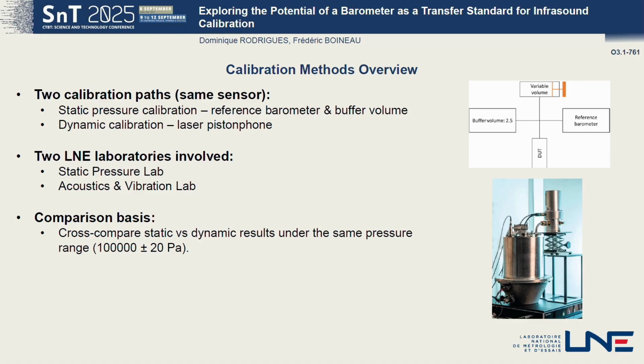the Infra-UV project. So one key point here is that to provide an accurate comparison basis, we asked the Static Pressure Lab to calibrate the barometer in a similar linear range to the one used in infrasound. So typically only 10 or 20 Pascal. So we asked them to calibrate the sensor at plus or minus 20 Pascal around the atmospheric pressure, which is approximately 1,000 hectopascal close to Paris.